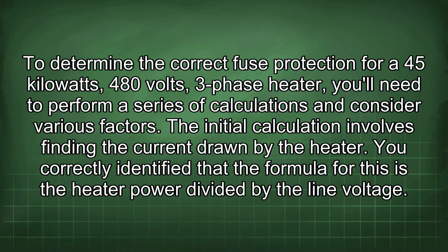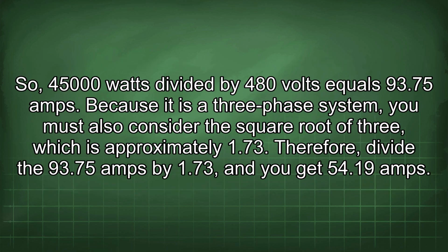To determine the correct fuse protection for a 45 kilowatt, 480 volt, three-phase heater, you'll need to perform a series of calculations and consider various factors. The initial calculation involves finding the current drawn by the heater. You correctly identified that the formula for this is the heater power divided by the line voltage. So 45,000 watts divided by 480 volts equals 93.75 amps.